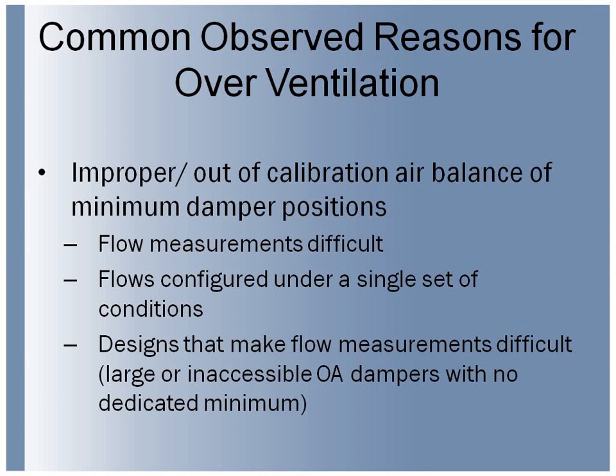The other thing that we're seeing is the outside airflow is typically configured under one set of conditions. So when the air balance folks come in, they're usually calibrating at one point, setting the system up at one point, as opposed to looking at the range of minimum and maximum flows for a variable volume system. So you have a system that may work or come close to working at that point, but as soon as it's off that point, we're either under or over ventilating.